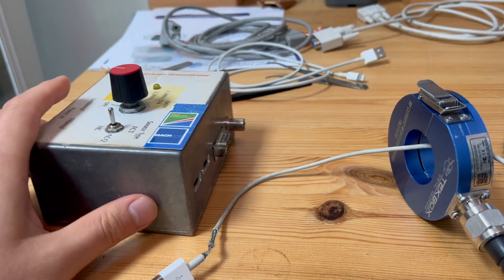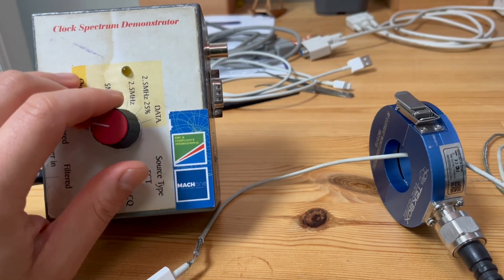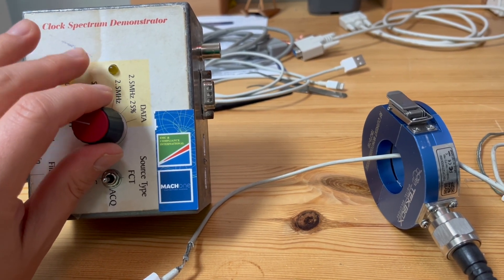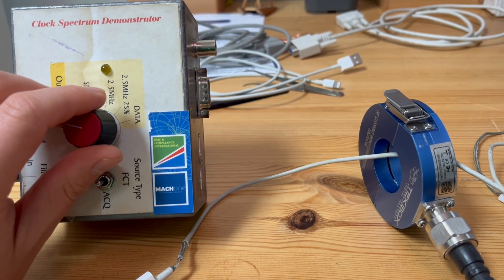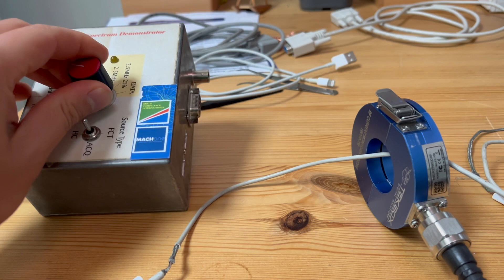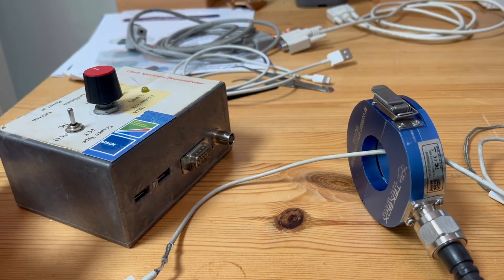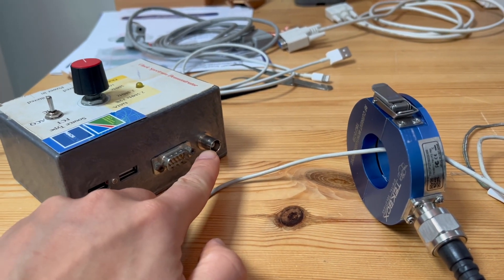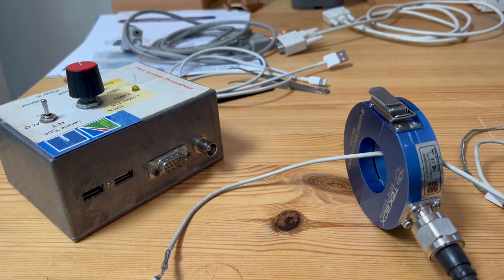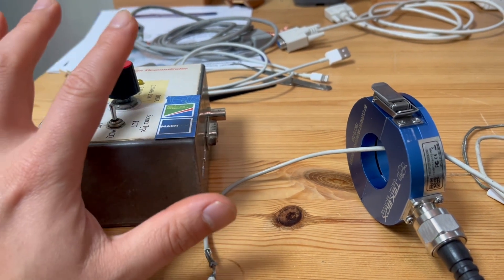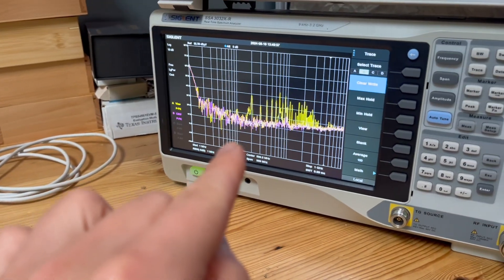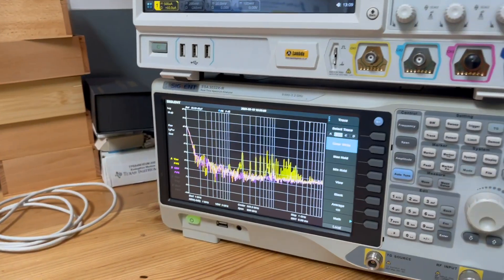For this episode, we're going to use this specially made demonstrating kit. Essentially, we have different types of tone generators inside this box where we can generate not only high frequency but also fast rise time signals. In order to analyze the cable shielding effectiveness, we have a few interfaces — you can connect a coaxial cable, a D-type shielded cable, or USB cables. The way we're going to analyze the shielding effectiveness is by clamping a current probe on a shielded cable, and then we're going to use both the frequency domain and time domain for our analysis.